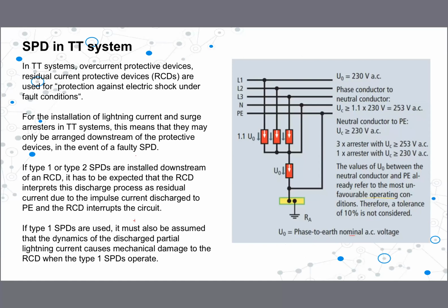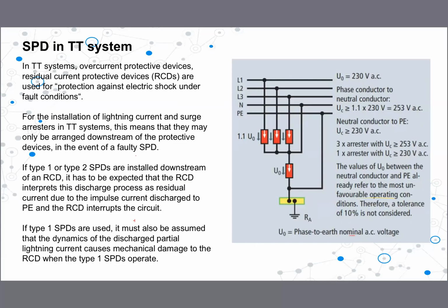Then let's look at how we install a surge protection device for a TT system. Now you know that in earthing systems, we have the TT system, we have the TN system, TN divided into two other systems, TNC, TNS, and the IT system, right? In different systems, the installation of SPD is not similar. In the TT system, we install it like this. We install surge protectors in each phase. Then after that, between the neutral and earth point. This is the correct way of installing a surge protection device.